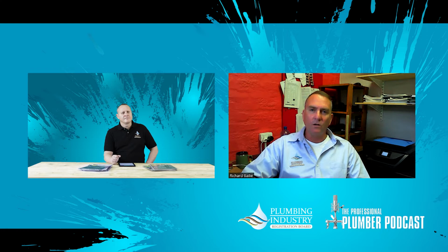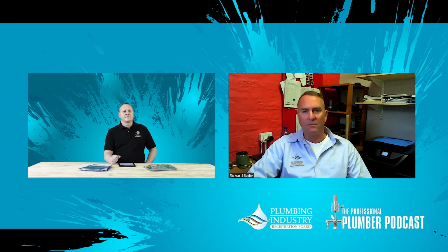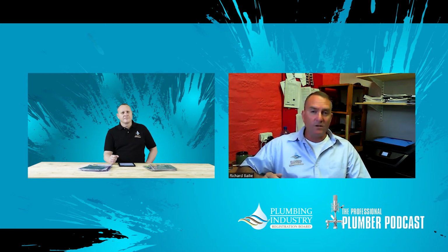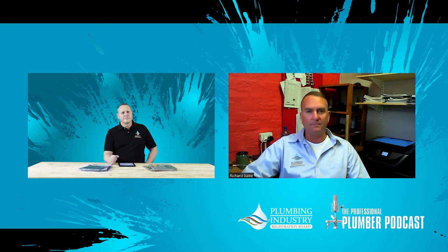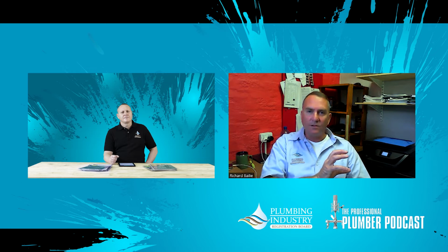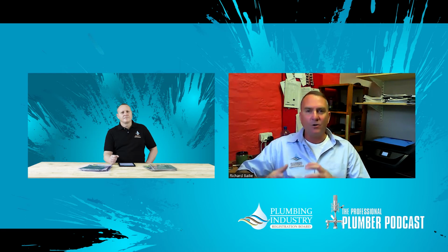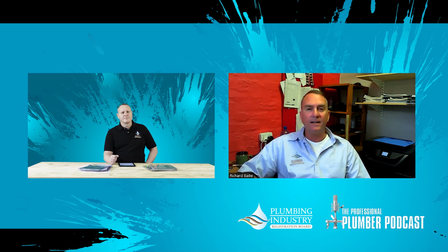A heat pump will draw the coldest part of the geyser off into the pump, heat it up by no more than 2 or 3 or 4 degrees Celsius, and then return it to the geyser, usually close to the top of the geyser. The heating of the colder water in the geyser by 3 or 4 degrees Celsius and putting it in the top of the geyser, that's your mixing effect. If you just leave that to its own devices, what you are essentially doing is inserting lukewarm water into the top of the geyser. And that's where you're going to start to draw off the hot water for usage.